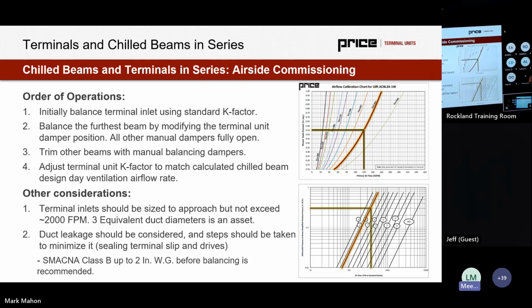And generally the rule of thumb here would be SMACNA Class B up to 2 inches of water gauge should be tested before balancing to make sure that we don't have too much duct leakage. That's a great thing to specify if you're using these products in series with one another. Of course, there's other options like low leakage terminals do exist. However, there's a cost add associated with them, and you're probably having to seal the ductwork downstream and still test the system anyways. So it might be more ideal to seal it in the same method that you'd seal the ductwork.